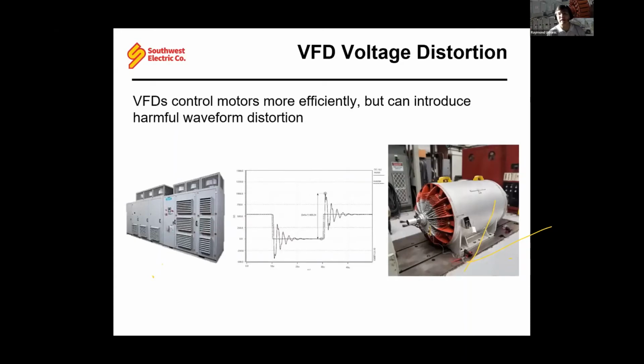The last thing we're going to look at is going to be the voltage distortion and damage we get from harmonics. In most motors today, I would say maybe even the majority of motors that are run in industrial facilities, at least the larger ones, are going to have some kind of harmonic distortion, waveform distortion, usually from VFDs. The drives almost always introduce that distortion.